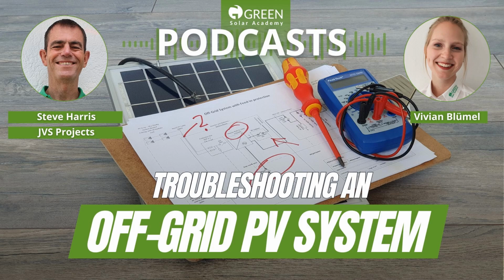The next area of faults are the actual connections into the fuses on PV strings. They will work loose over time, because you have this expansion and contraction as the cables warm up and cool down. It's a common thing. Once a year maybe, check and tighten everything if you can. And I know sometimes it's difficult if it's a long way away, but if you can, make a visit back to site a month later. Go and check the tightness of all the connections, because guaranteed, you can have made them as tight as you want on the installation, they will work themselves loose. And you don't need it to be very loose before it becomes a hotspot.